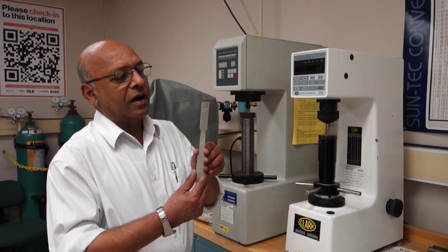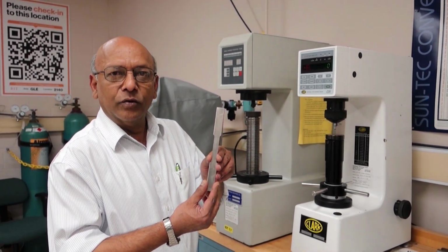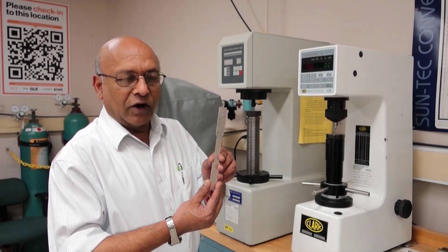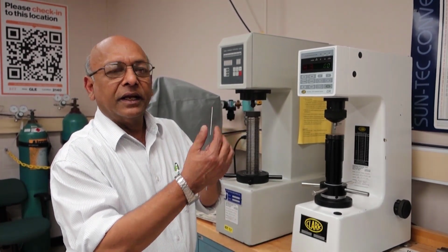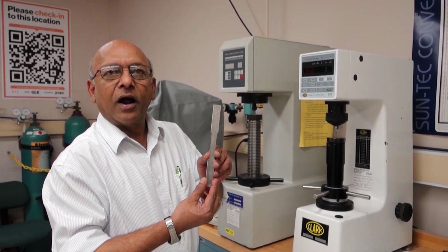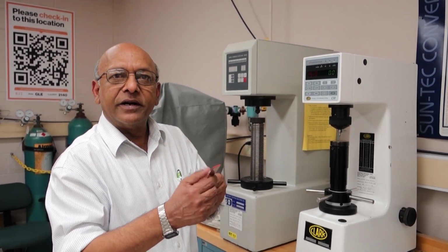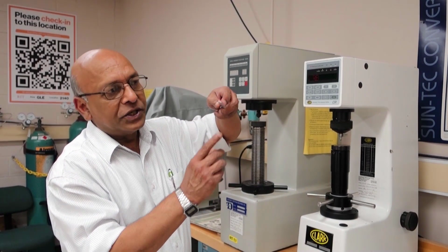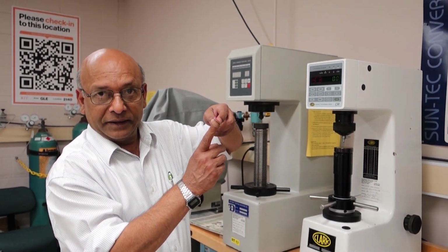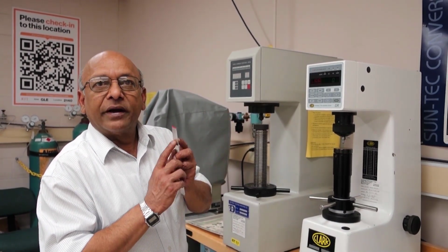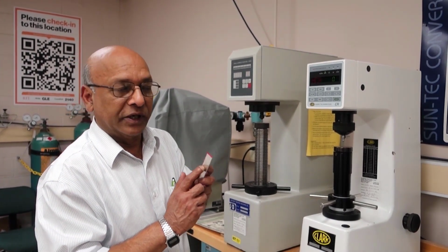I want to measure the hardness of this tensile specimen. It is made out of 6061 aluminum, a soft non-ferrous alloy, and you can see that the specimen is quite thin. If I were to make a regular Rockwell B measurement on it, the large load of 100 kg is going to punch the indentation through, and I would be able to see it at the back of it. So I cannot do a regular hardness B testing on it. I'm going to do superficial testing.